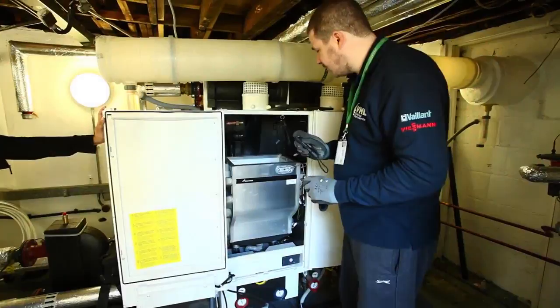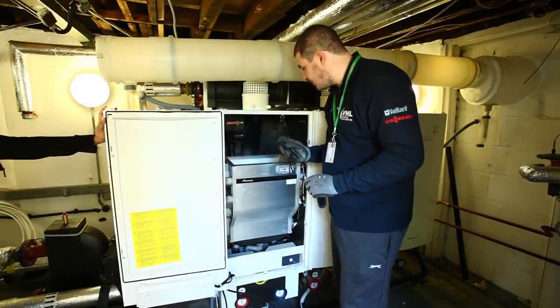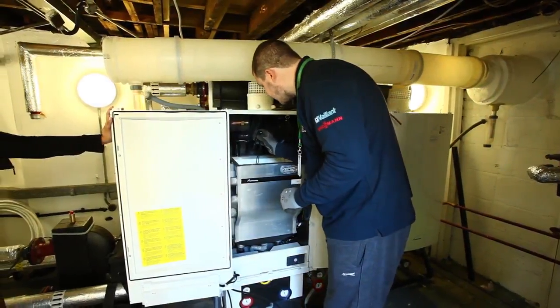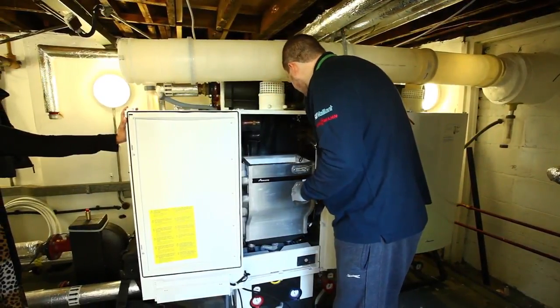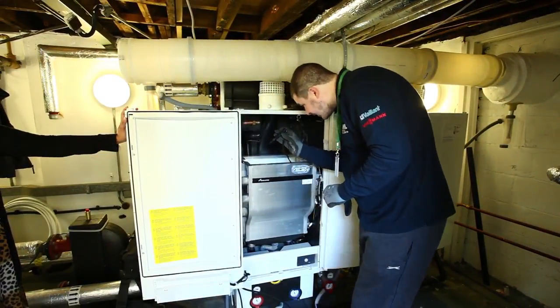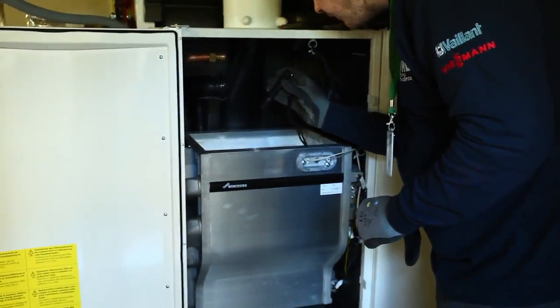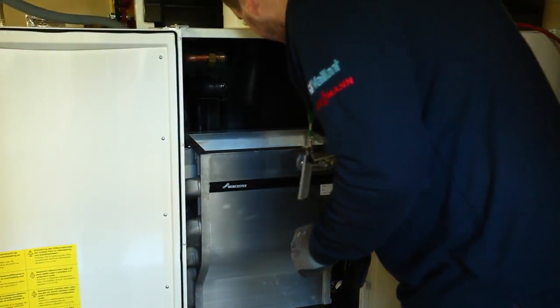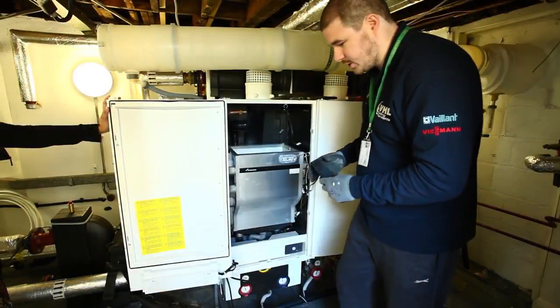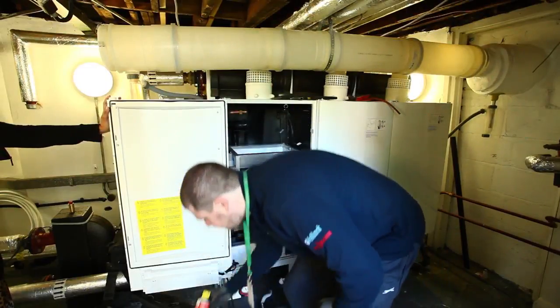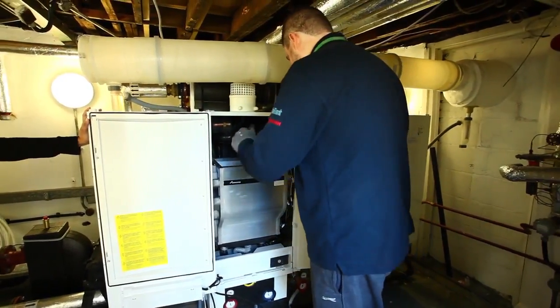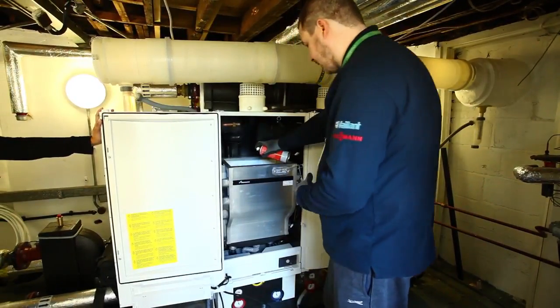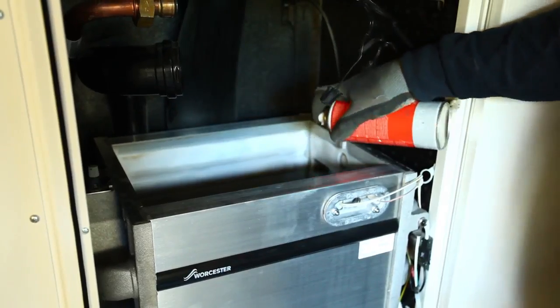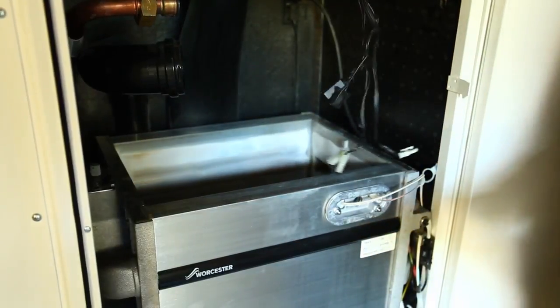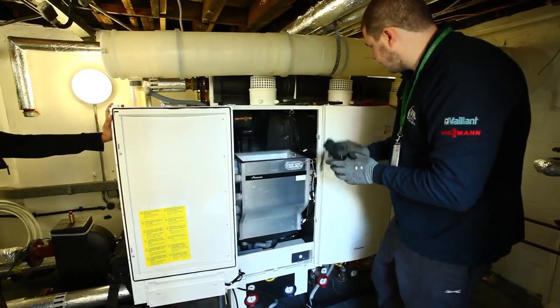So after we expose the burner, we expose the main heat exchanger. We just merely inspect it on our initial installation to make sure there is no leaks, the ignition is fine and there's no signs of distress inside the burner. And this is all looking very good and I'm very happy with it. Right, so after this we just clean it with an air duster, keeping it away from our eyes, just in case there is any debris that may be sitting on the heat exchanger. Then we begin the reverse process of putting it back together.